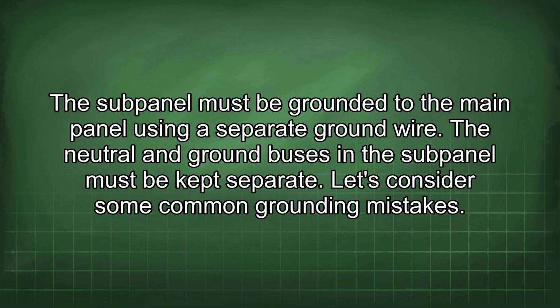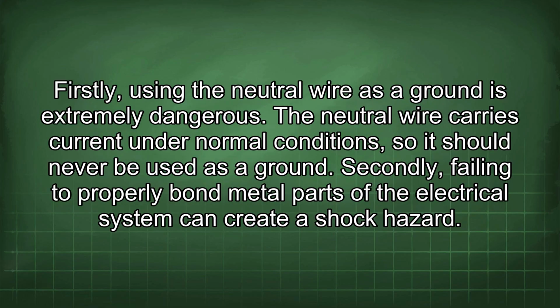Let's consider some common grounding mistakes. Firstly, using the neutral wire as a ground is extremely dangerous. The neutral wire carries current under normal conditions, so it should never be used as a ground. Secondly, failing to properly bond metal parts of the electrical system can create a shock hazard.